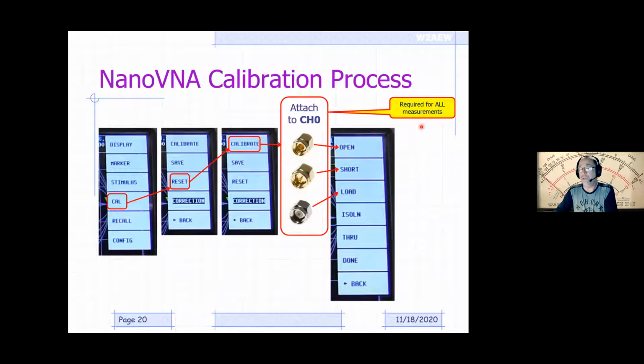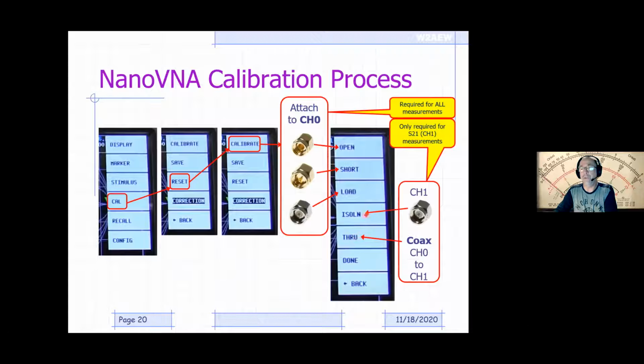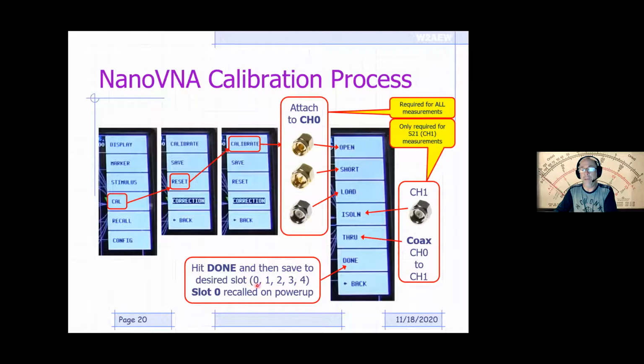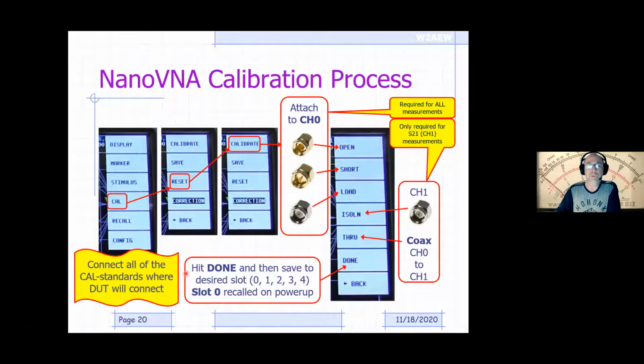If you're going to be making 2-port measurements, then you also want to do the isolation and through measurements. For the isolation measurements, you leave the 2 ports disconnected or apply a load to channel 1 to kind of isolate it and shield it, if you will. And then the through measurement is just connecting a coax between channel 0 and channel 1. Once you've done the calibrations that you need, or run through these cal standards, you hit done, and then it'll bring up a menu to ask which slot you want to save that calibration to. And if you select slot 0, again, that's the one that's recalled on power up. And ideally, you want to connect all of these cal standards at the location where your device would normally attach. That would remove the phase and delay and the loss, if you will, of your interconnect and calibrate them out of your measurement.